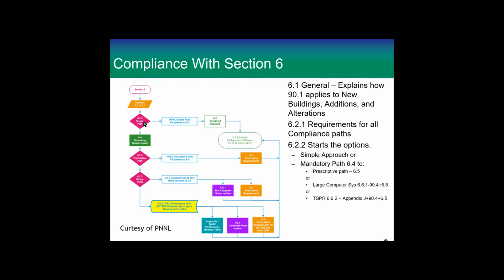Now 6.2.2 is a simple path. The ASHRAE mechanical is the only, well, there's 2 of us now that have simple paths. We've had it for a long time. Now, the simple path is the only thing I'll tell you about that does not have to go to the mandatory, because all the mandatory things that apply to simple path have been included in the simple path. So they're there, you just don't have to go through 6.4 to get to them. Now, that goes off and you go the simple path.